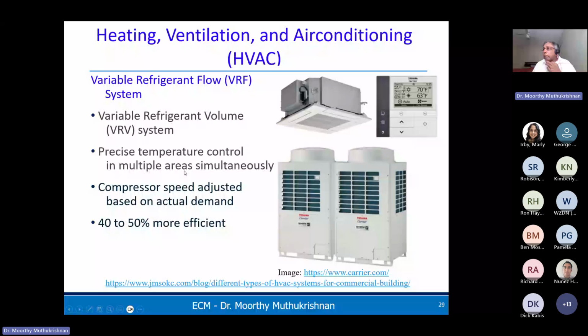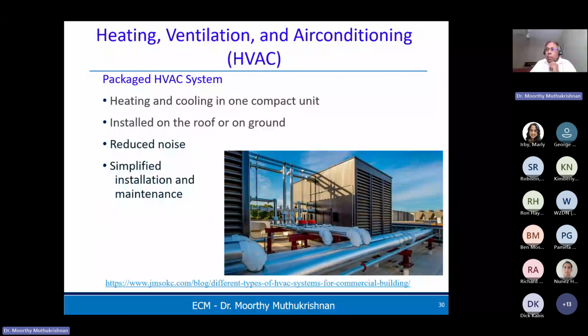The next one is called a package system. The package system is normally one single unit. It looks like a big box, as you can see here, and it is located either on top of the roof or on the ground somewhere outside. It contains both the cooling and heating. They say that it's easy to install compared to the multi-split system, and everything is contained in this single unit, with reduced noise and so on. Again, it all depends on the particular building. In some cases, the roof will not be able to hold such a heavy weight, so you won't be able to install this on the roof, and you have to install it on the ground.